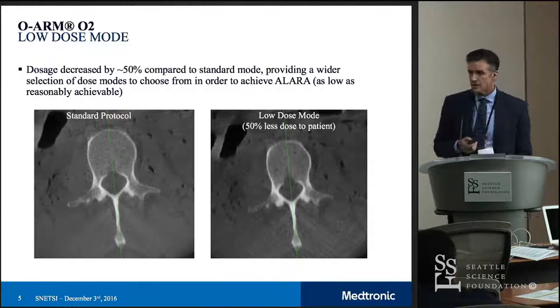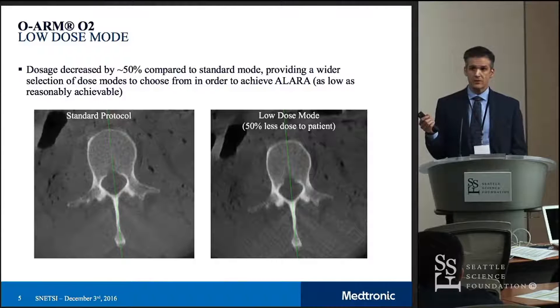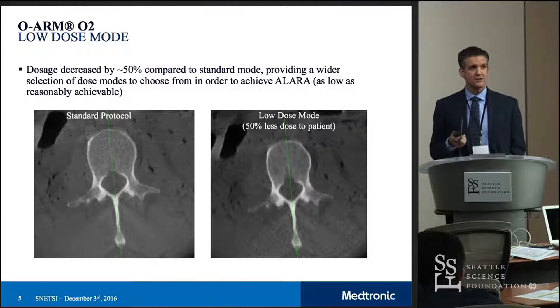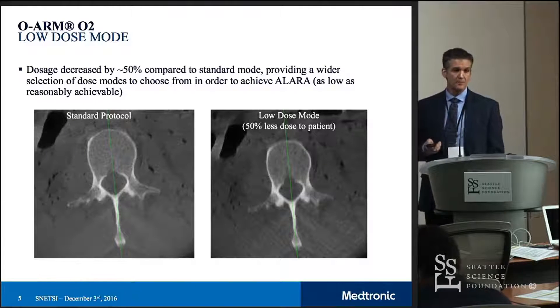Here's an example of an image on the left with our standard protocol, and an image on the right with low dose mode. This takes about twice as long to process, but it's half the dose. It is also using a faster computer than what was available on the previous generation of the O-arm. This is a trend that is going to continue — reduced radiation exposure while either maintaining or potentially improving image quality.